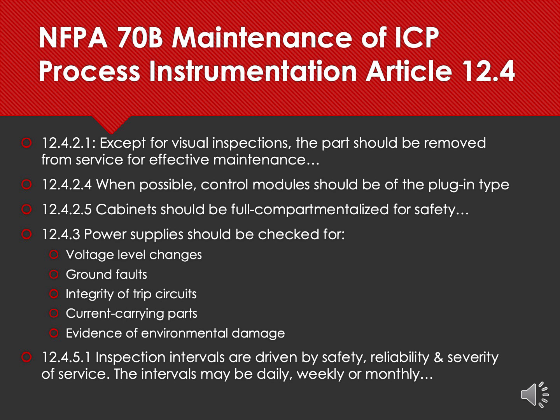Current carrying parts need to be maintained both in terms of continuity, for making sure the connections are not oxidized or whatever, and that they are properly connected and tightened down in place, making sure they exist for that, and also for if they've been exposed to overcurrent or overvoltage situations where it becomes apparent that they got hot or there's flashover of the insulators, and any of those flashover of the insulators would render the system in need of replacement parts. And finally, if there's environmental damage to the equipment, again, this can be corrosion, but it can happen from just the environment that you're in.